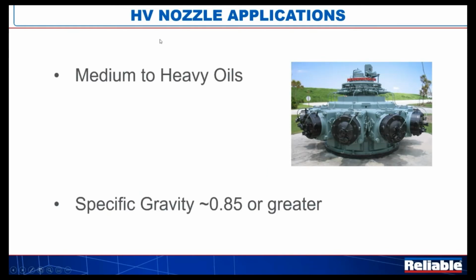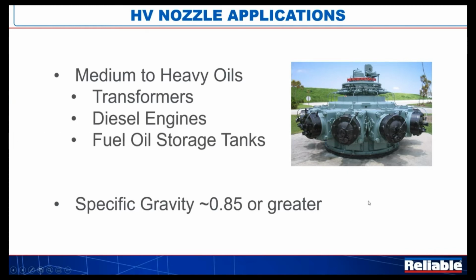So where are we going to see these used? High velocity nozzle applications are less defined by flashpoint, at least it seems when I was researching, than by specific gravity. So you can find tables that will give you the specific gravity of different oils and fuels and vegetable oils and all kinds of stuff like that. Medium to heavy oils, specific gravity of 0.85 or higher. So where do we see these? Again, in the transformer world, diesel engines, fuel oil storage tanks, bunker oil, things like that, and lube oil systems.